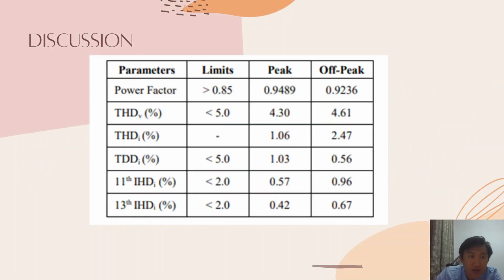So based on our result, we got our power factor at the peak equal to 0.9489, which is very good, because it is above 0.85.